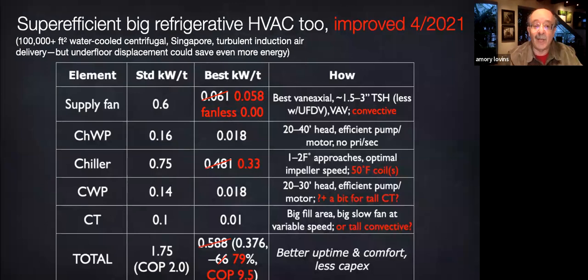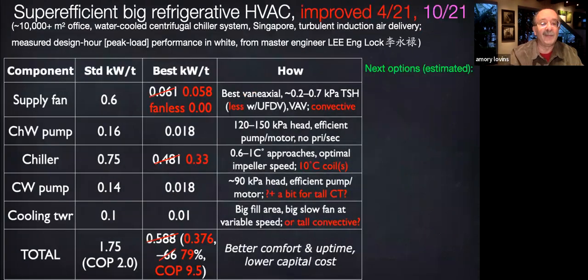And that incurs a slight extra pumping head. And then the chiller could drop to 0.33 kilowatt per ton. Look at that red number in the middle of the chart, using optimal 10-degree coils. So Mr. Lee's red markup improved that 3x efficiency gain he already got 20 years ago to as much as 5x.